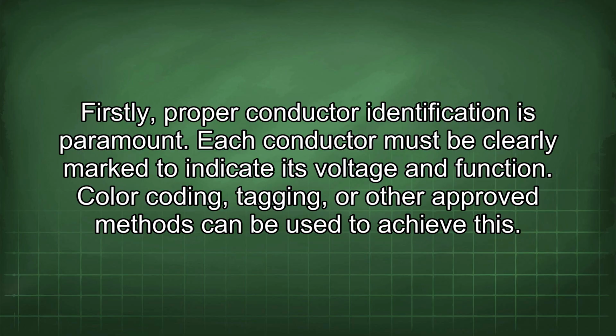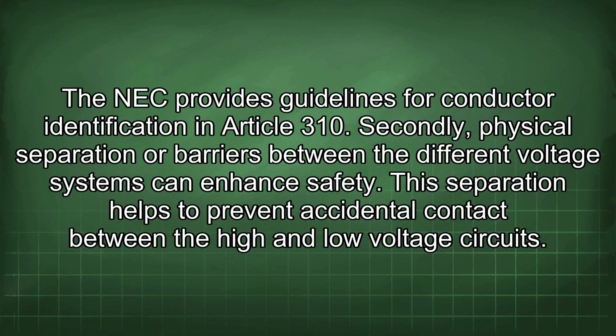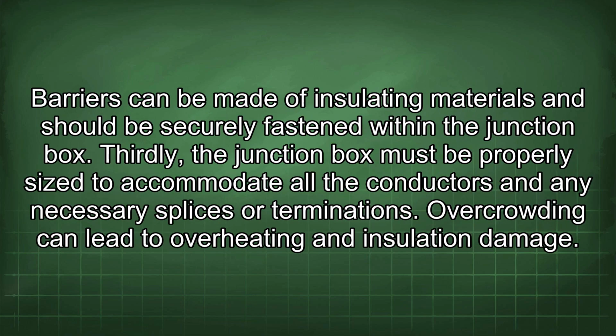Firstly, proper conductor identification is paramount. Each conductor must be clearly marked to indicate its voltage and function. Color coding, tagging, or other approved methods can be used to achieve this. The NEC provides guidelines for conductor identification in Article 310. Secondly, physical separation or barriers between the different voltage systems can enhance safety. This separation helps to prevent accidental contact between the high and low voltage circuits. Barriers can be made of insulating materials and should be securely fastened within the junction box.